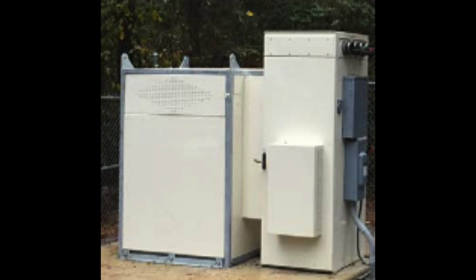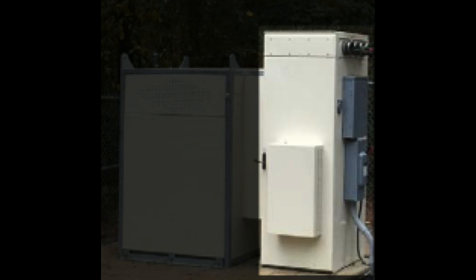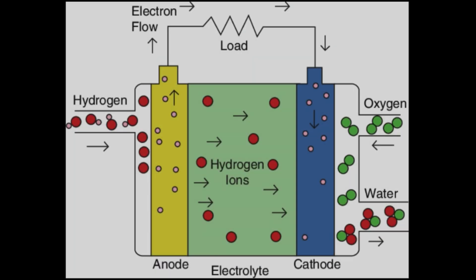While not nearly as complex as a generator system, it does have a few additional parts. There's a separate fuel system, usually consisting of hydrogen tanks and some plumbing in an enclosure, although larger fuel demands are deployed in single tanks. Within the fuel cell system enclosure itself, there are several pressure reducers, a water drain with heater, and ductwork to the outside, as well as the actual fuel cell device. When a hydrogen fuel cell is operational, it produces some liquid water — hence the drain and the heater — as well as moist air with some unused hydrogen, hence the ductwork to the outside.